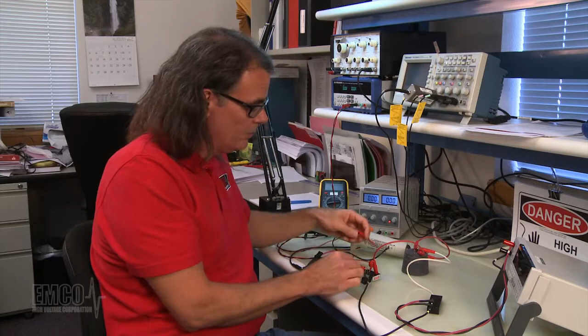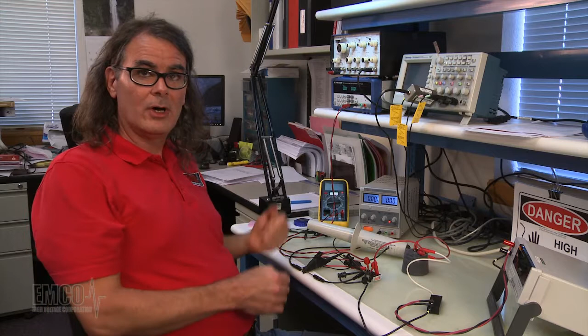So now I can power up the power supplies, and an important thing to note is that your input voltage power supply must always be the first to be powered on, and there is a minimum of a 100 millisecond delay between turning on the input voltage and the programming voltage. Of course, with a manual test, that's easy to accommodate, but if you're doing an automated test where you're sequencing your power supplies through a computer system, you have to make sure that the input voltage is applied before the programming voltage. So we've got 0 volts on the input voltage and on the programming voltage.